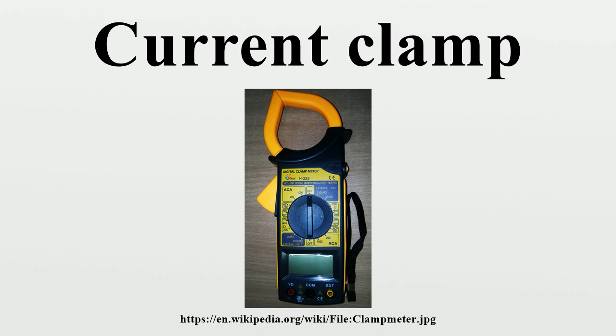Less expensive clamp meters use a rectifier circuit which actually reads mean current, but is calibrated to display the RMS current corresponding to the measured mean, giving a correct RMS reading only if the current is a sine wave. For other waveforms, readings will be incorrect when these simpler meters are used with non-sinusoidal loads such as the ballasts used with fluorescent lamps or high-intensity discharge lamps, or most modern computer and electronic equipment. Readings can be quite inaccurate. Meters which respond to true RMS rather than mean current are described as true RMS.